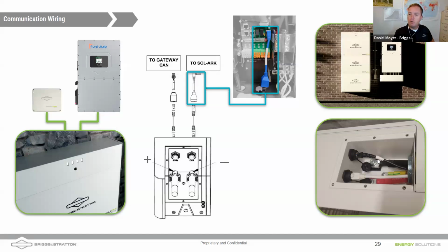We're looking at the top of the controller up here, negative, positive. This is what's going out. That black Ethernet cable is going over to the inverter. That white Ethernet cable is going over to the energy track. There is an optional grounding here. A lot of AHJs wouldn't require that.